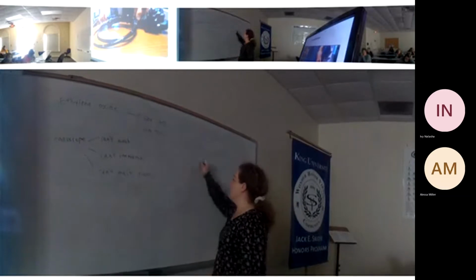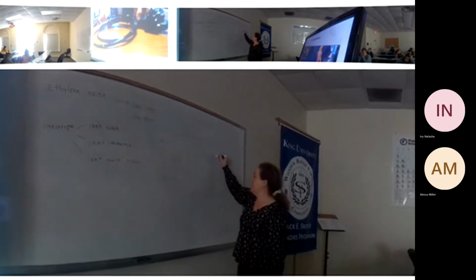So the best option for sterilizing advanced technical equipment is to put it in a chamber. You're gonna love this beautiful chamber I'm drawing right here. Here we go. Here's the endoscope. You put it in a sealed chamber and you flood the chamber with ethylene oxide gas, and you let it sit there for a certain amount of time.